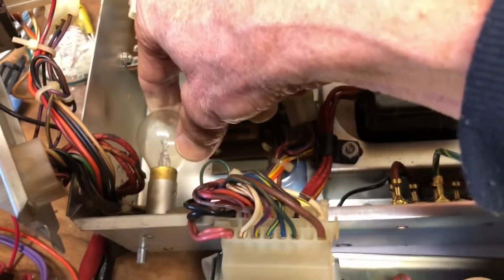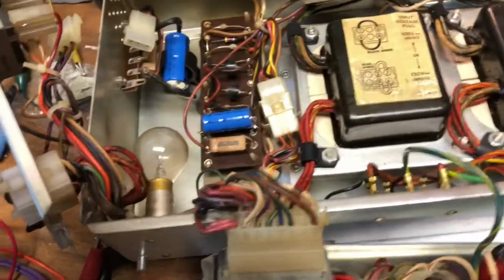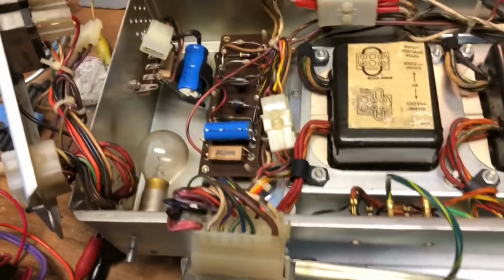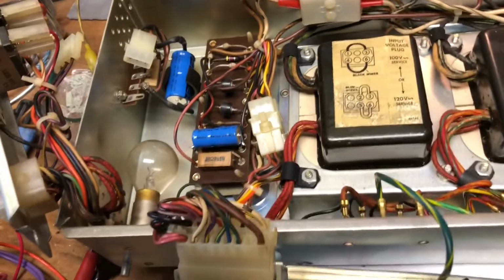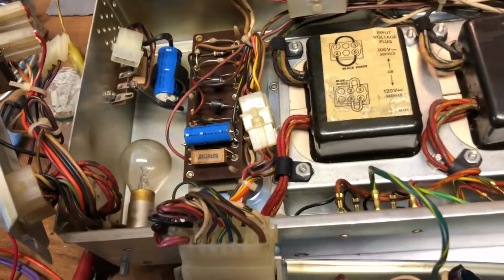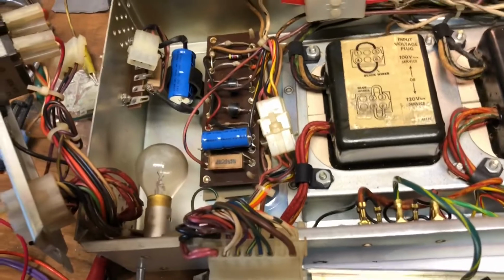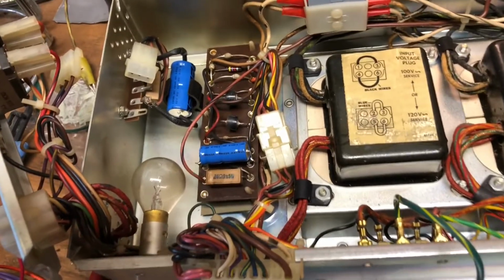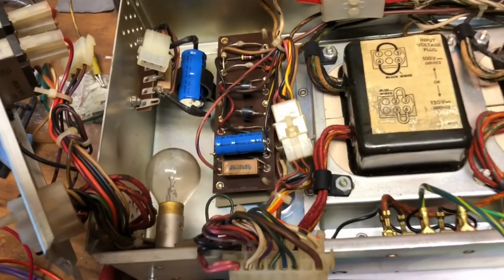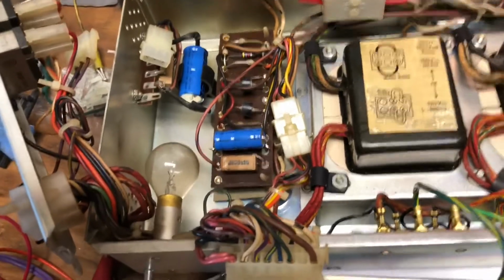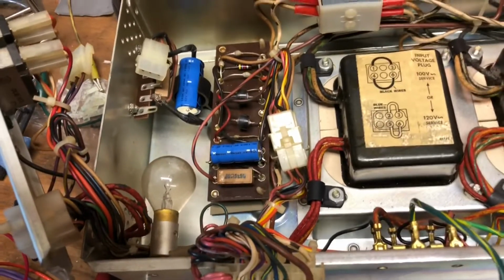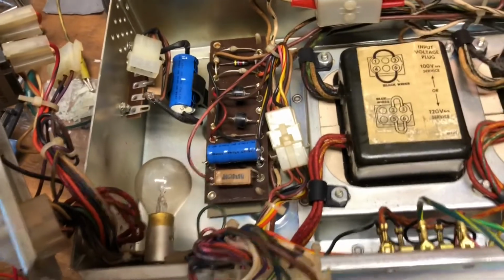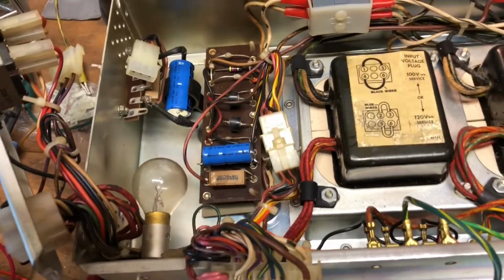Then I also check this current limiting bulb. All you have to do is take it out and check continuity. If the coil shows some resistance, it can be from anywhere from 4 ohms up to 20 ohms. That's fine. All you want to really be sure is that the bulb isn't burned out, in which case the filament will be open and you'll get an open circuit.